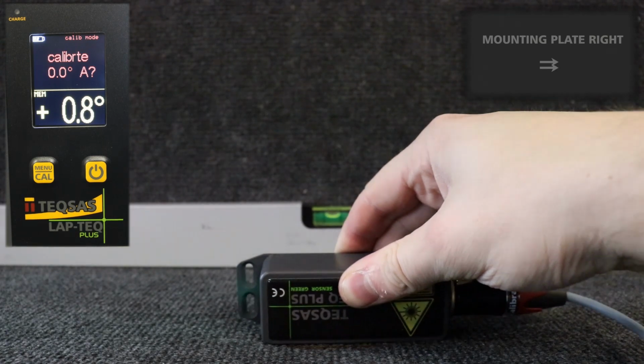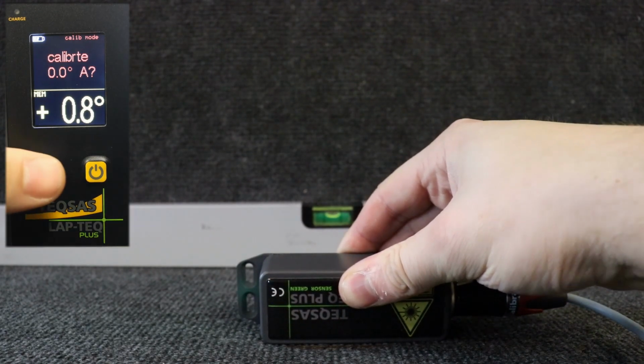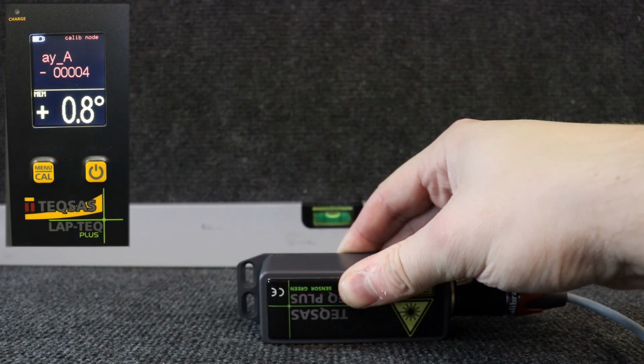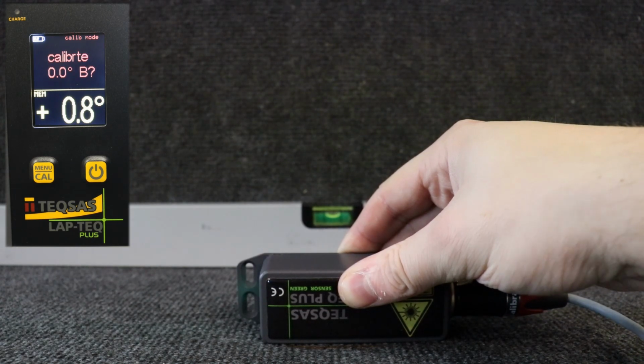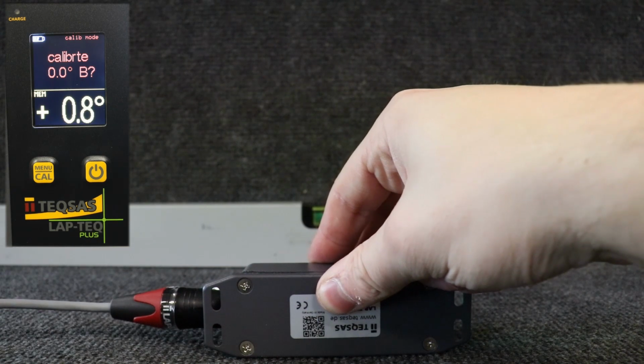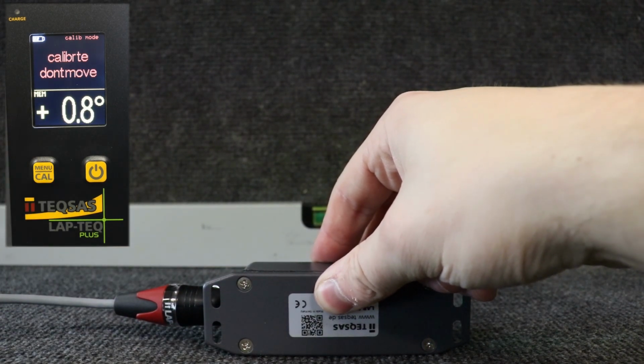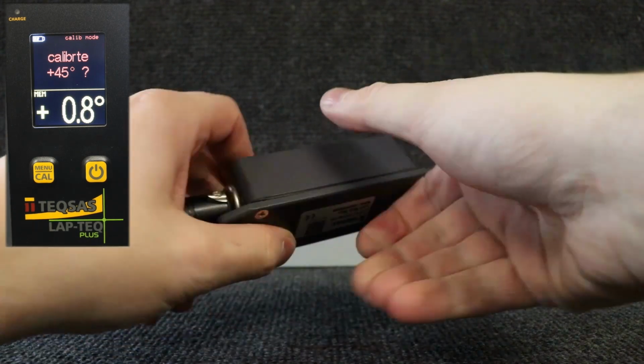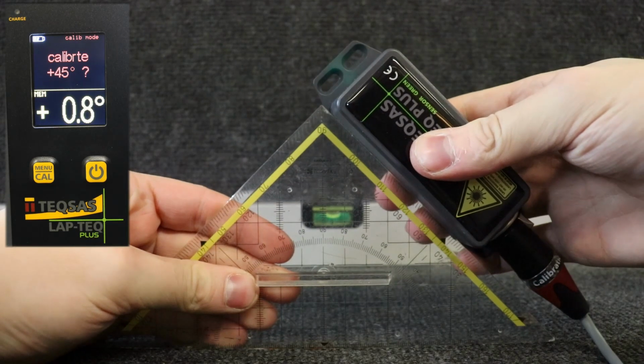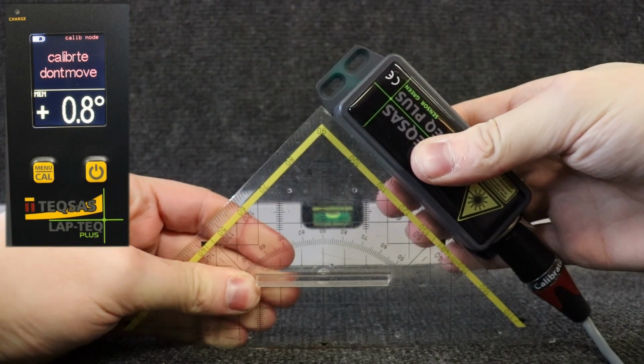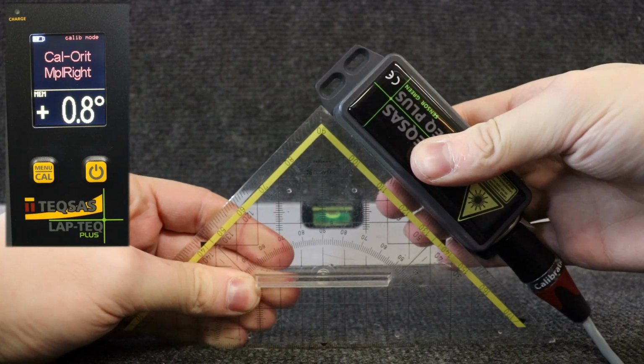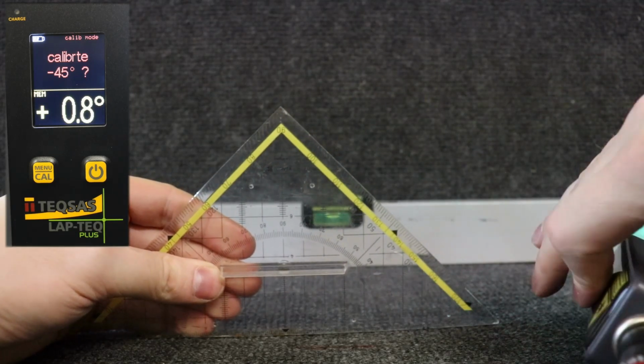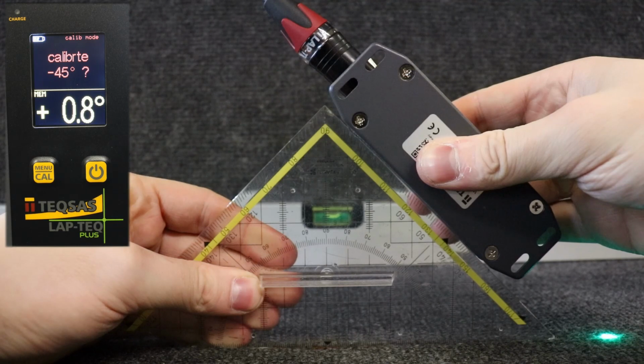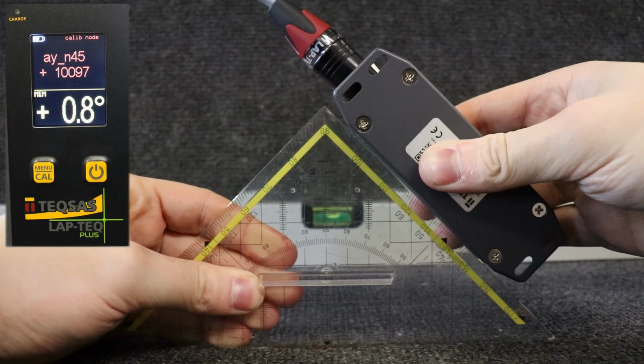Again, this is seen from the side of the XLR connector in the direction of the laser beam. First step is 0.0 degrees. Second step is 0.0 degrees in the opposite direction. Third step is plus 45 degrees. And the last step, as before, is minus 45 degrees. At the end of this fourth cycle, the display reads calibration complete, which means all calibration data has been gathered for all four mounting orientations.